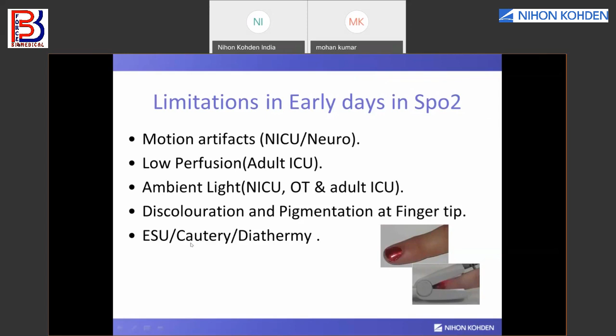And in case of discoloration and pigmentation, whenever there is nail polish or some kind of color on the fingernails, the SpO2 was not coming properly. So these were the limitations. And in case of OT, electrosurgical units, cautery machines or diathermy machines used to affect the SpO2 readings. To overcome all these things, we have the NPI algorithm, the Nihon Kohden Pulse Oximetry Perfusion Index algorithm, which overcomes all these problems.